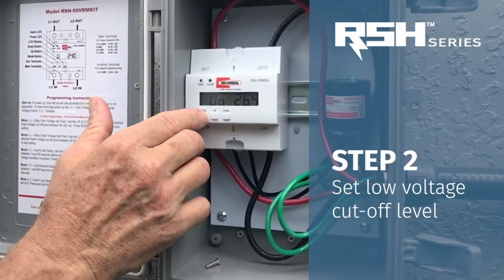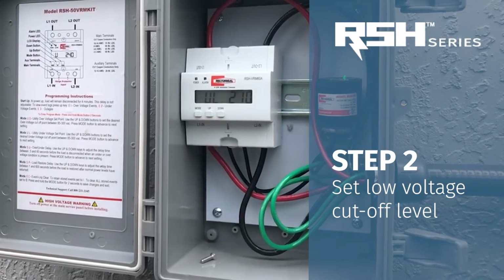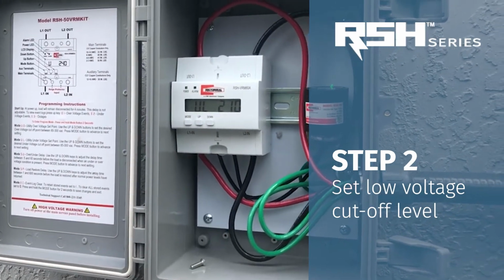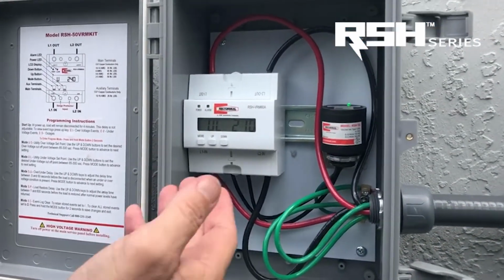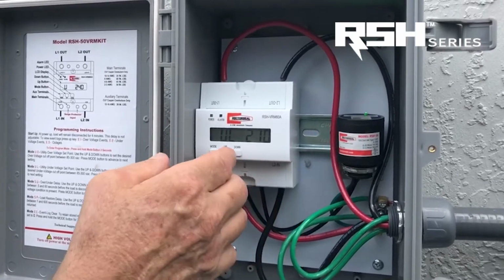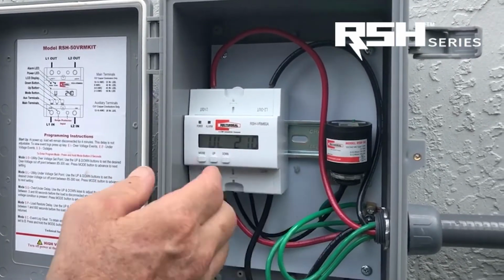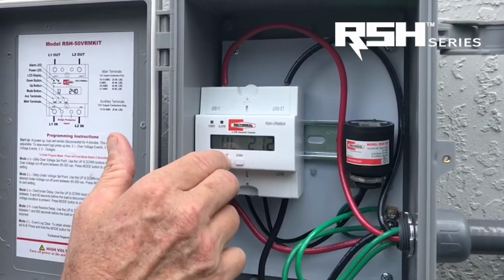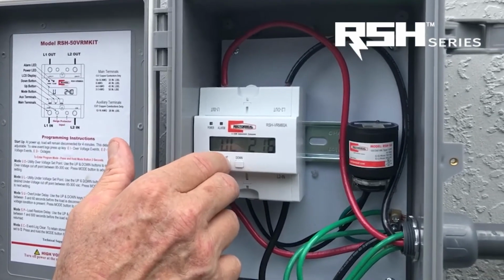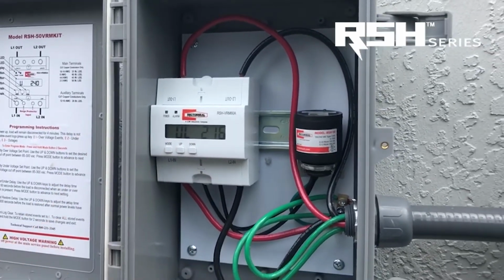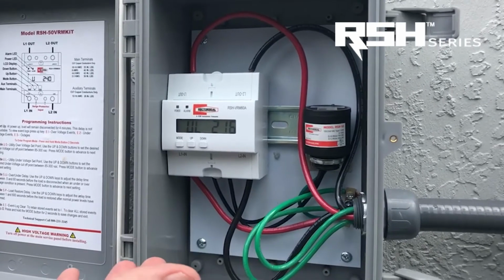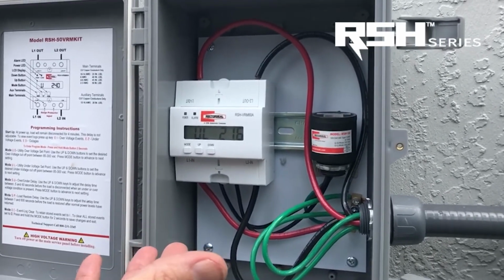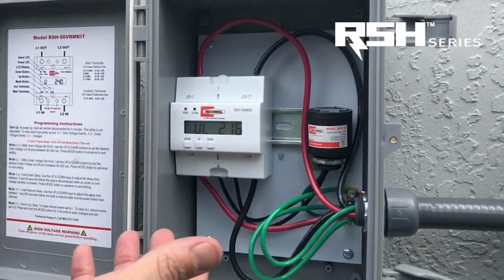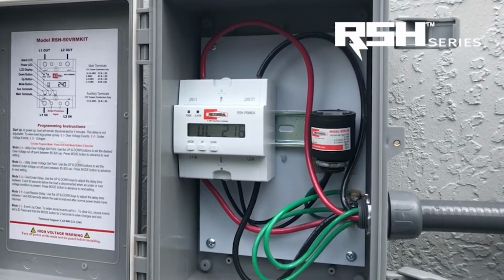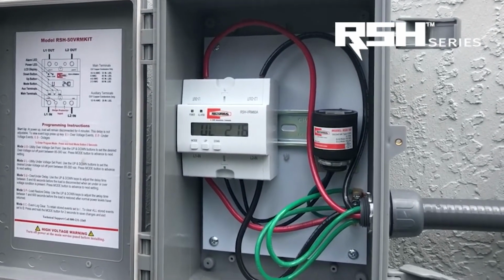Next mode is going to be the low voltage level, or the brownout level, where we cut off power. So we're at 240 volts. 10% would be 216, so we're going to program up to 216 volts. So now we have our window set.